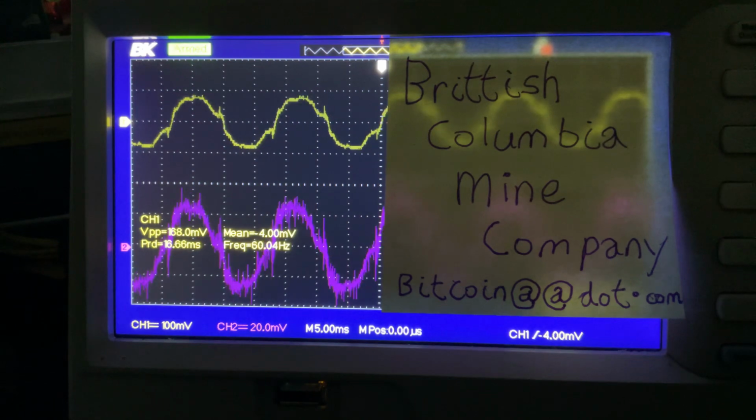So you look at the power waveform there, like I'm cleaning power here, right? We got a room that has some equipment in there. That's a clean room, clean power room. It's subtracting a lot of the radio noise that's in the power grid. As you can see, there's not much radio noise in the grid. You can see it in that's the purple one, that's hot to ground. Okay, hot to neutral, that's the yellow waveform.